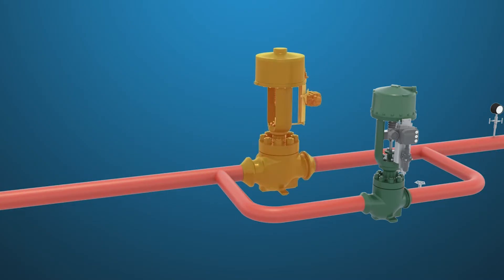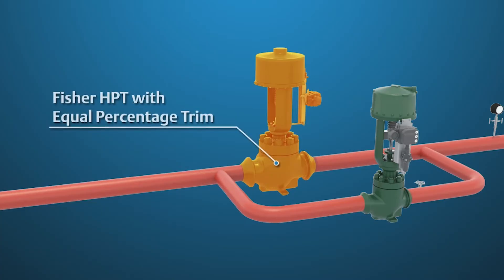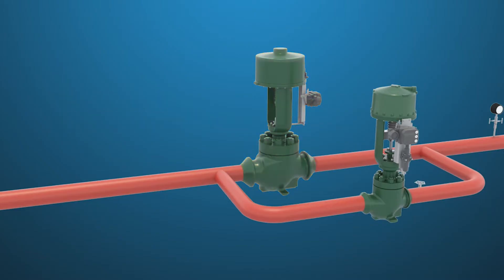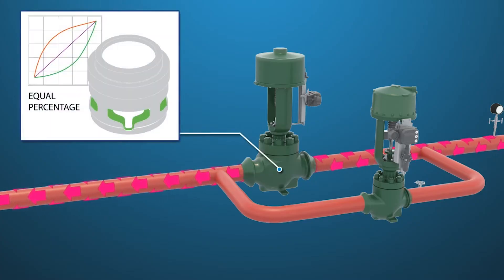An ideally-sized regulating valve system will have the main feed water regulator valve CV at about 20% open, equivalent to the CV of the startup valve at 80% open. As a rule of thumb, the feed water valve should have an equal percentage trim installed to offset the performance characteristic curve of the feed pump.